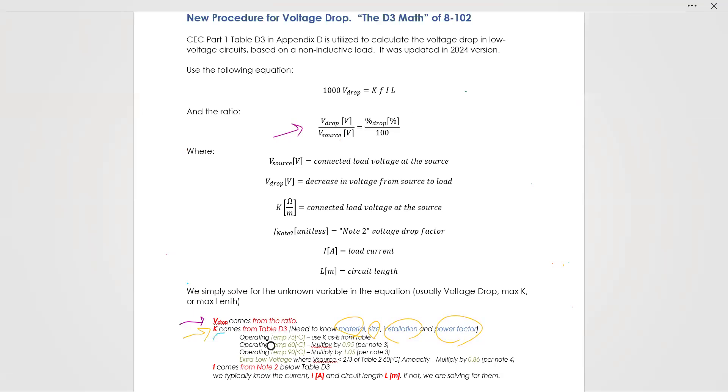The K value comes from table D3 that I just showed you when we circled material, size, installation, power factor. We go into that table, and all we do is get the value - we get the K value. But, if the operating temperature is 75 degrees, then we're good. We use it just as it is from the table.